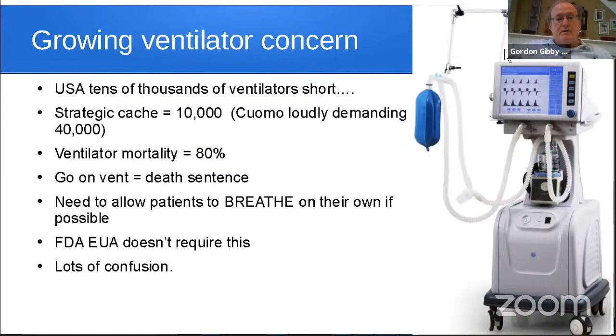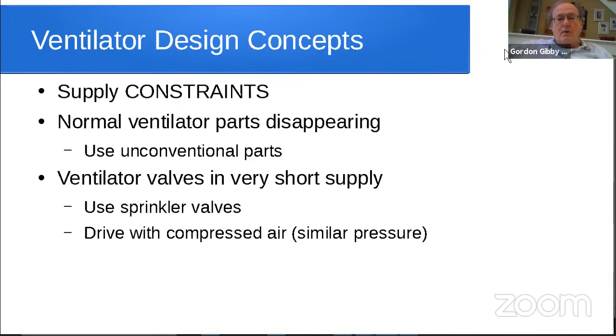Ventilator valves were in very short supply, so we were going to use sprinkler valves from your lawn sprinkler. We were going to drive it with compressed air, which is a similar pressure to the pressure that drives normal ICU ventilators, by the way. So when the University of Florida came to me, they had an airway system. It was a beginning airway system, but they had no way to turn it on and off. And in just about 24 hours, I turned this around and created my famous Sunday morning kitchen table demo.